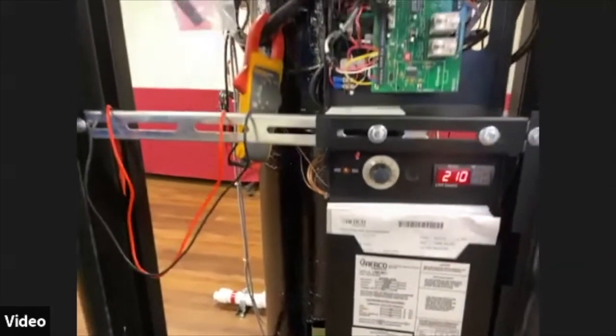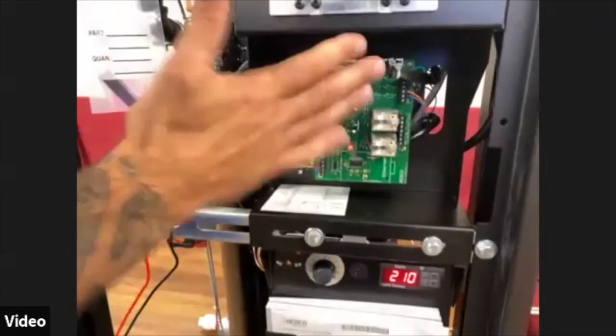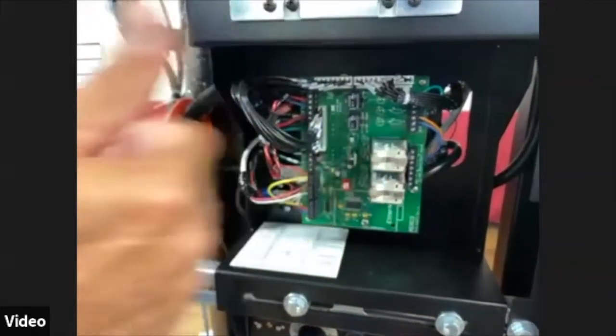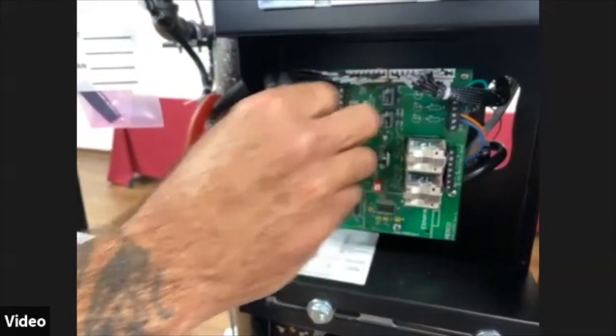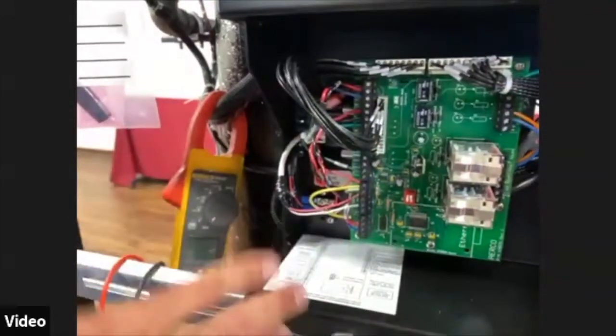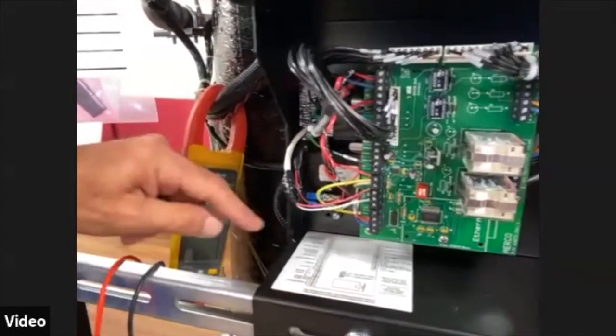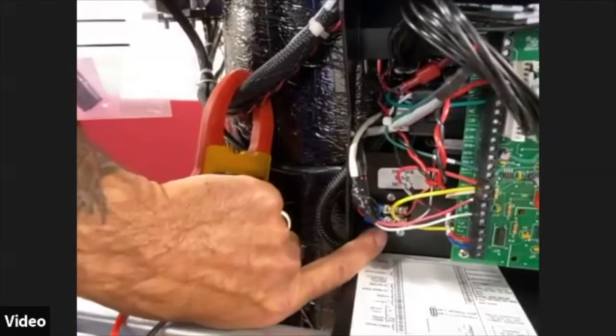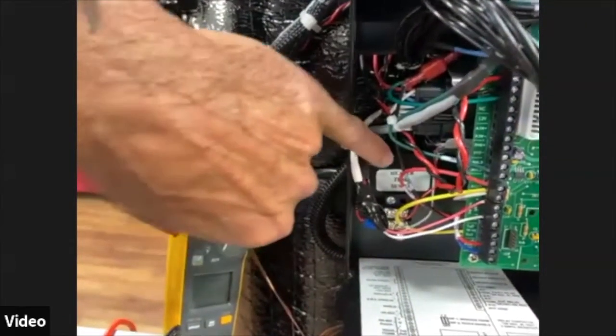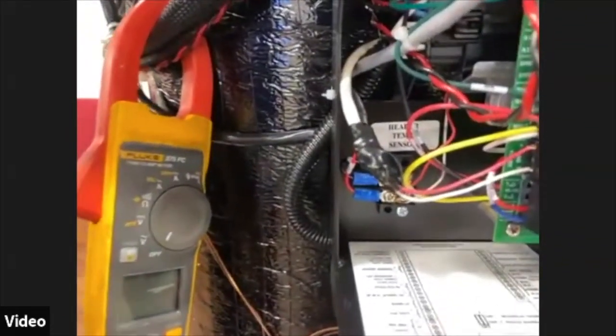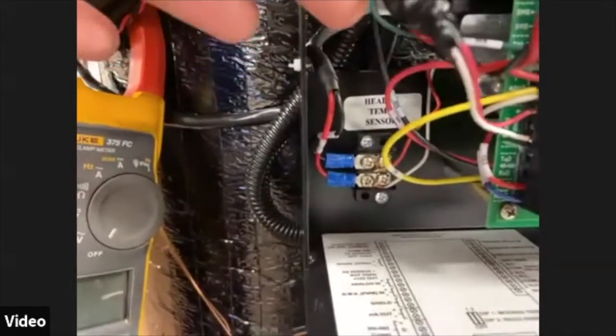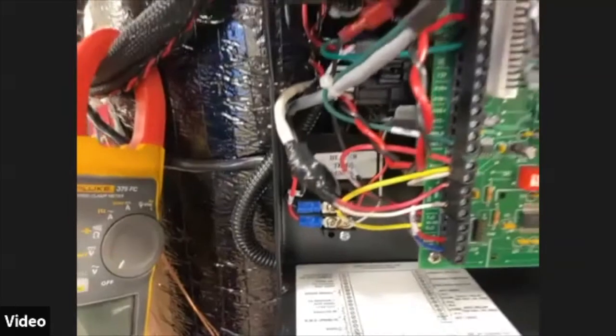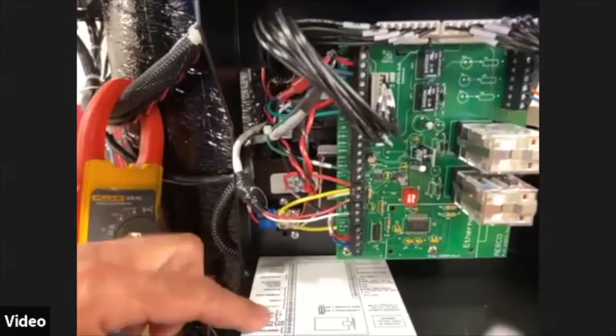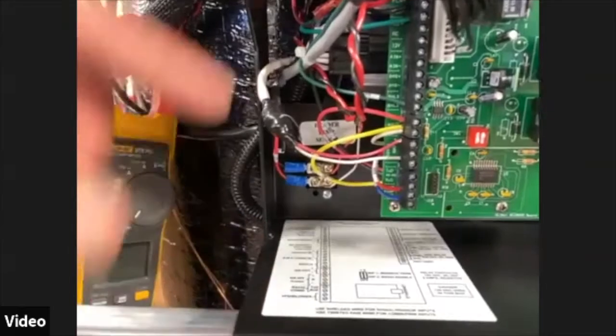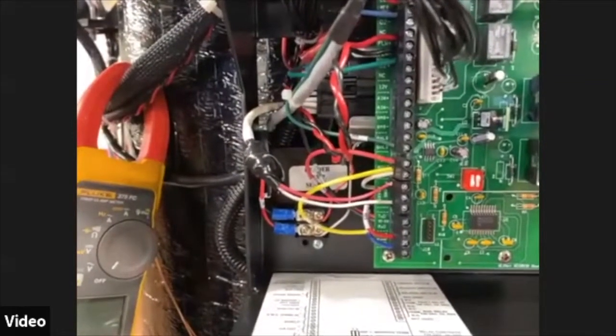And then we come up to the I/O board. So this is an input-output board. Sometimes it's just pass-through for communications or for specific safeties. So a couple of things I'm going to talk about are header sensor. So this is where we would land our header sensor. And it's actually marked up here for you, header temperature sensor. The board is all marked, and there's also a sticker below it, if you can't see some of this because of the wiring going through here.